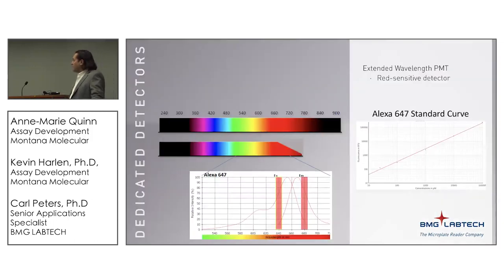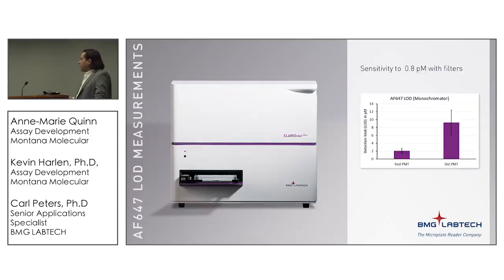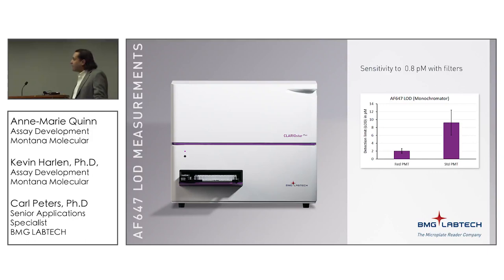The last feature to discuss is the extended wavelength PMT. Not only is it useful for detecting far red-shifted fluorophores, but traditional PMTs show a drop-off in performance even for fluorophores that aren't extremely far red, such as Alexa 647. The new extended wavelength PMT shows very good performance over a wide concentration range, and comparing it with the standard PMT we have a much better LOD performance — with filters you can get down to a sensitivity of 0.8 picomolar for Alexa 647.